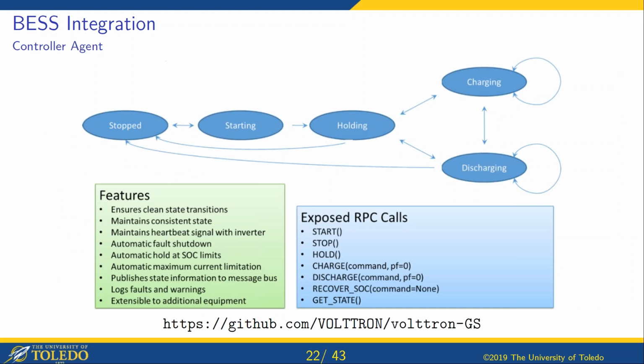The battery agent we wrote that controls that is a fairly simple state machine, and for the time being does manual control - manual from the perspective of applications running automated algorithms. Eventually we'll probably add modes for handling other things from the MESA standards, like following frequency watt curves. But this gives us the ability to send charge and discharge signals to it, and it manages any faults and warning conditions the battery might have, and propagates that up to us where we need.